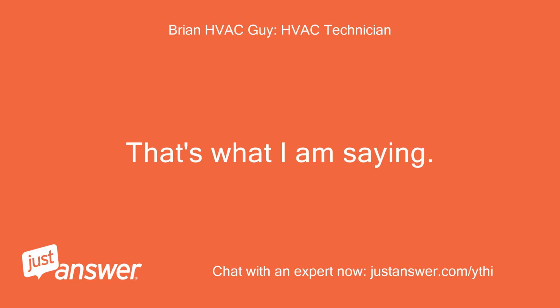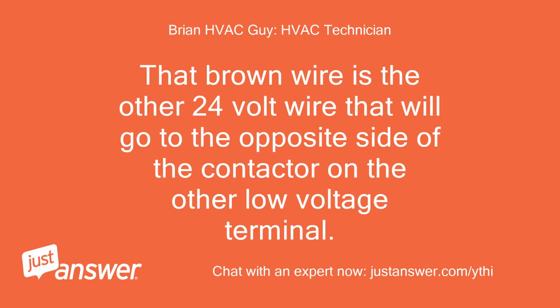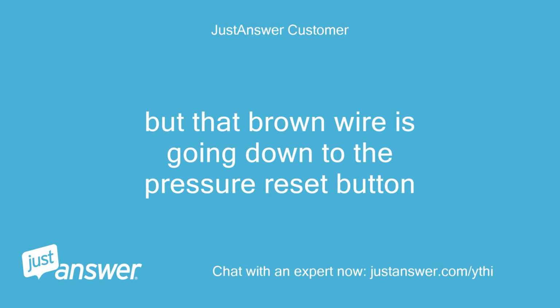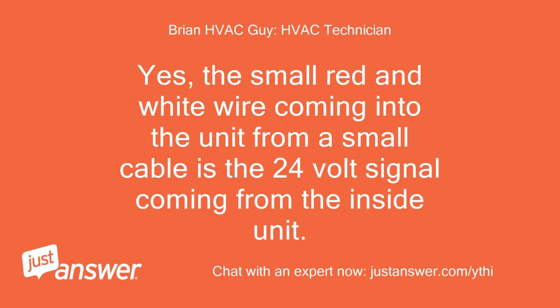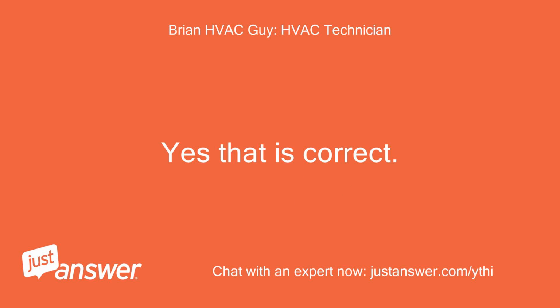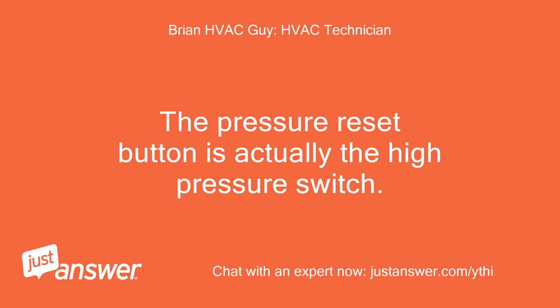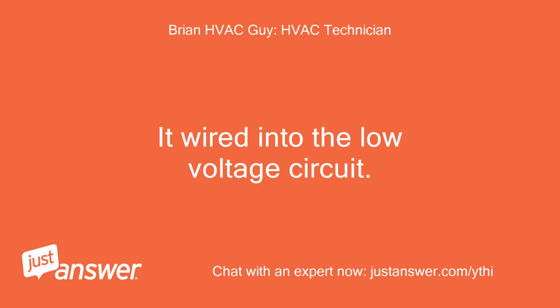That's what I am saying. That brown wire is the other 24-volt wire that will go to the opposite side of the contactor on the other low-voltage terminal. But that brown wire is going down to the pressure reset button. Yes, the small red and white wire coming into the unit from a small cable is the 24-volt signal coming from the inside unit. Yes, that is correct. The pressure reset button is actually the high pressure switch. It is wired into the low voltage circuit.